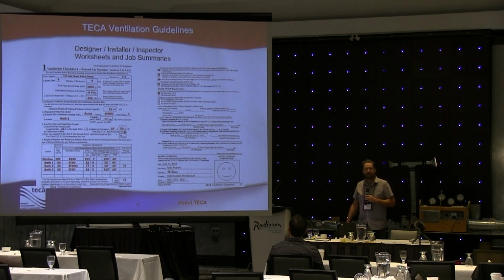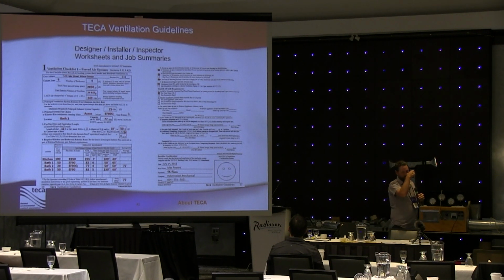Yes, in the back. Touched on natural draft appliances. Yes. They're putting these commercial grade hood fans in. Sometimes the burners don't even turn on because they're like 1200 CFM. Does your course teach you to compensate for that hood fan sizing? We do, yeah, absolutely. We talk about makeup air requirements to make sure that we're bringing air back into the building if we're creating a negative pressure situation.